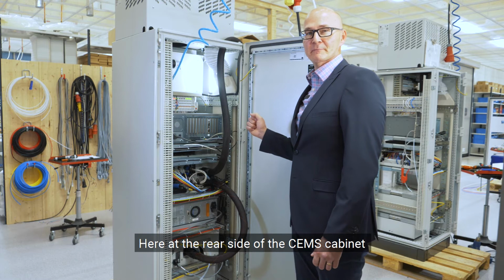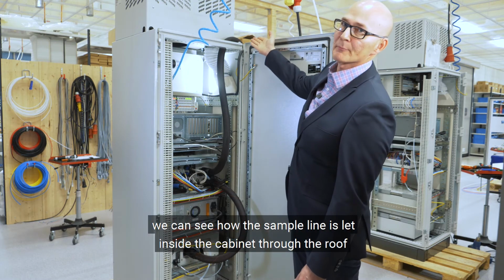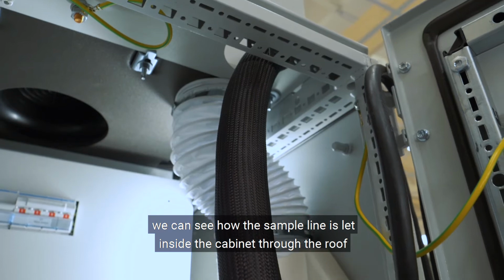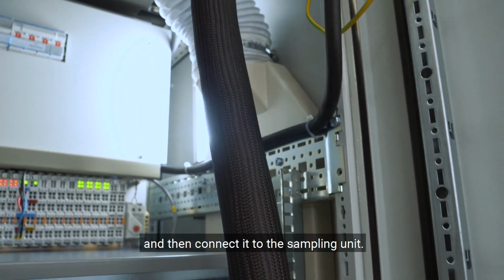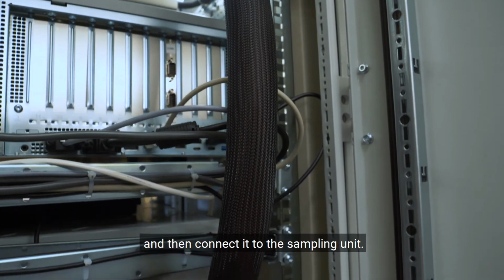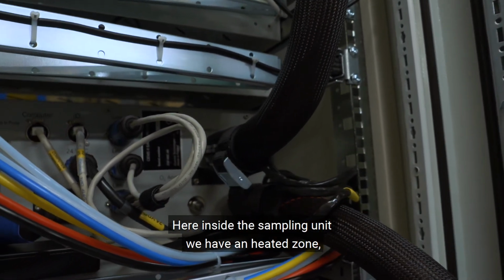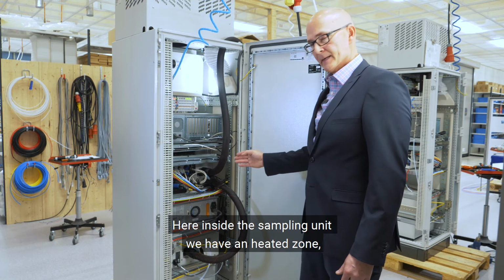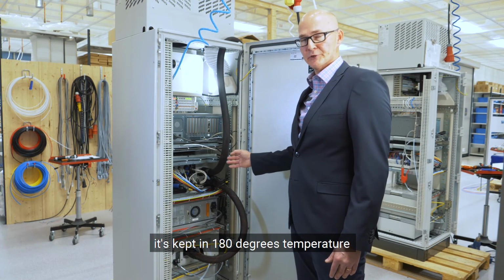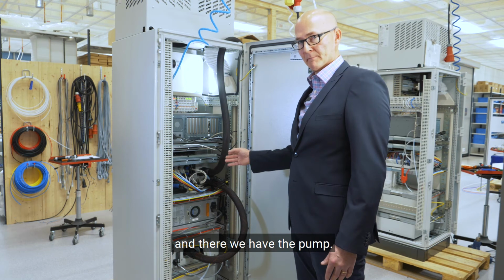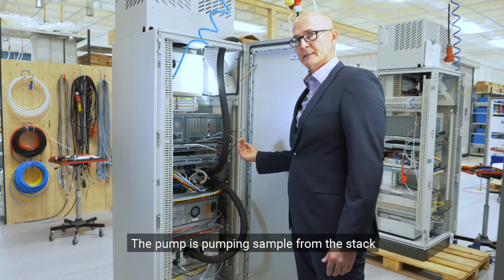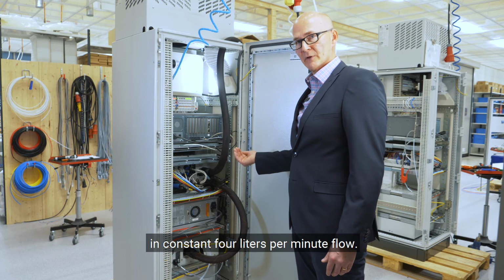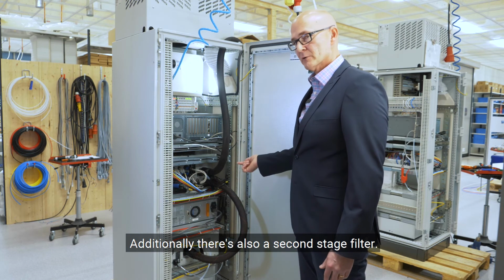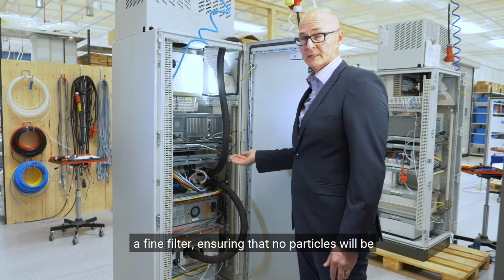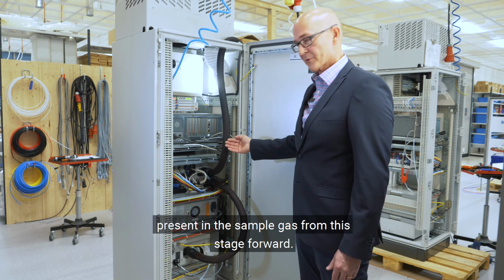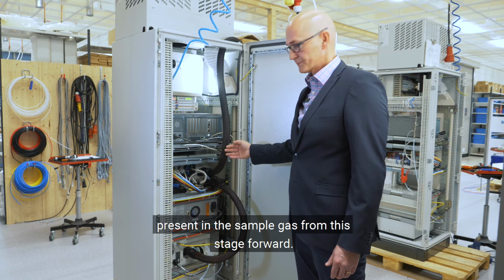Here at the rear side of the CEMS cabinet, we can see how the sample line is led inside the cabinet through the roof and then connected to the sampling unit. Here inside the sampling unit, we have a heated zone. It's kept at 180 degrees temperature. And there we have the pump. The pump is pumping sample from the stack in a constant 4 liters per minute flow. Additionally, there's also a second stage filter, a fine filter, ensuring that no particles will be present in the sample gas from this stage forward.